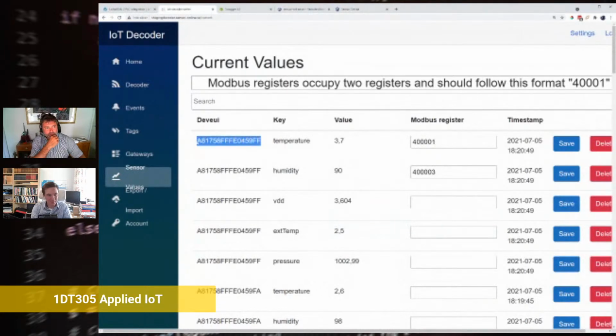Here we have the MAC address, the temperature value, which must be in a freezer. And here we can expose this value in a Modbus holding register, meaning a PLC or SCADA system can connect to this Modbus TCP slave and get those values in holding registers 40,001 and 40,003. So here you can put in 40,005 — should be odd numbers all the time — and press save. This is a nice feature.